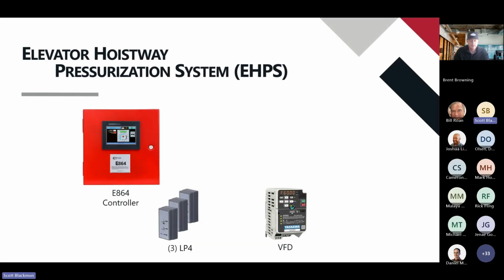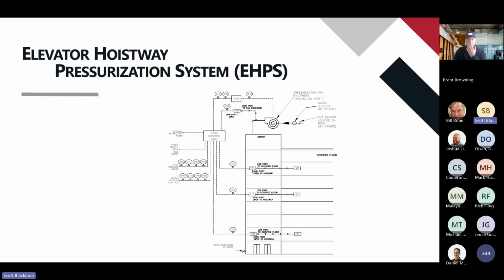When we're talking about elevator hoistways, basically the same kind of situation. The only thing that we need to keep in mind with elevators is that they have a little tighter pressure window. They don't want to go above about 0.25 inches on the elevator shafts. If you do, you're going to start to see door failures in that case.